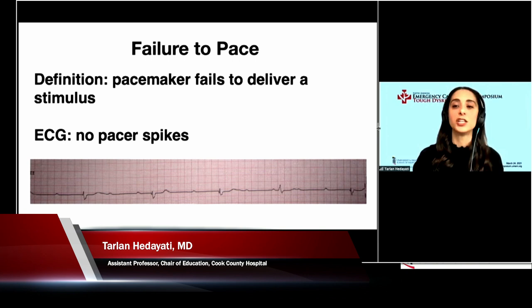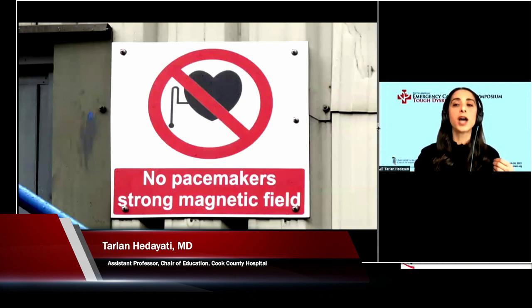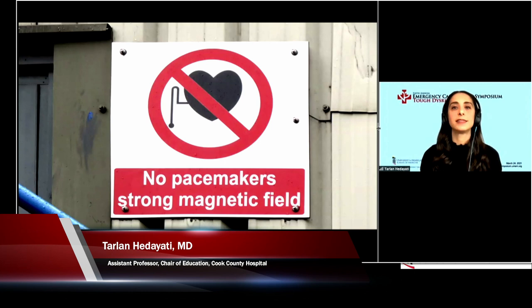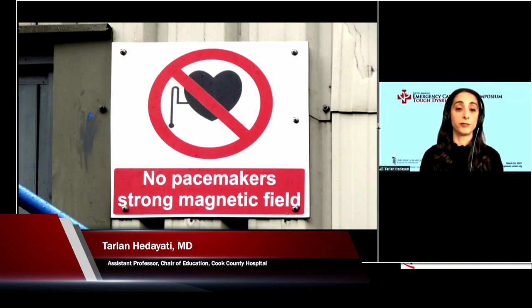What caused this problem? The most common cause of failure to pace is oversensing, meaning the pacemaker is overwhelmed by external signals. That can be from a strong magnetic field—you can see the sign here. You'll see these at the airport as well when you go through security, if you've been in an airport recently.